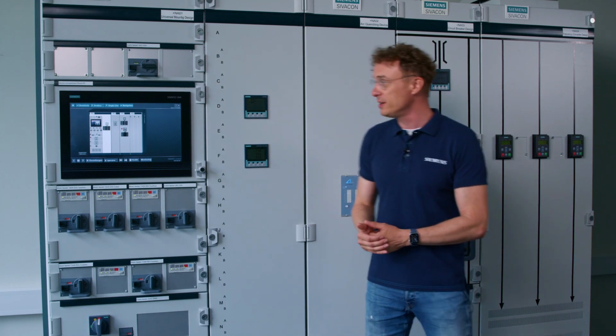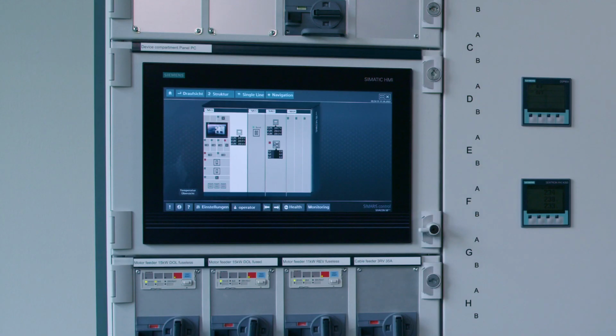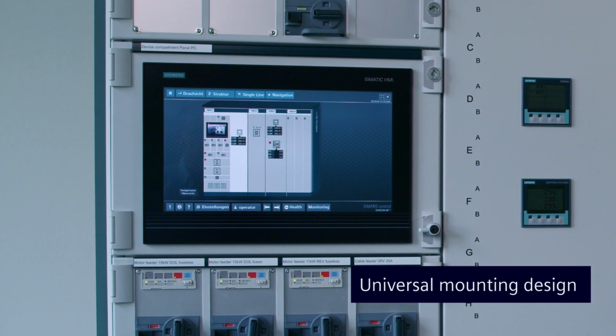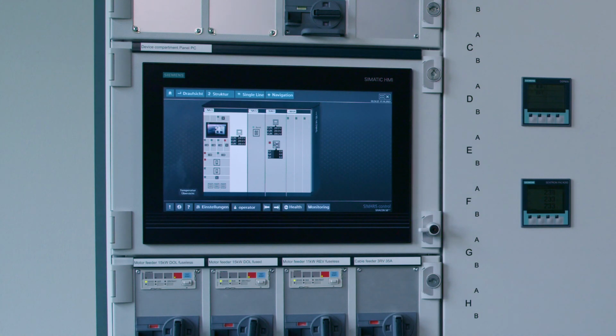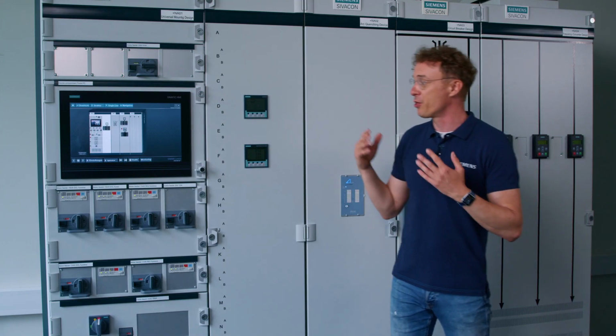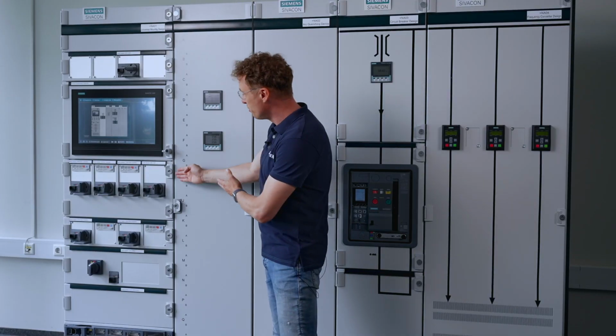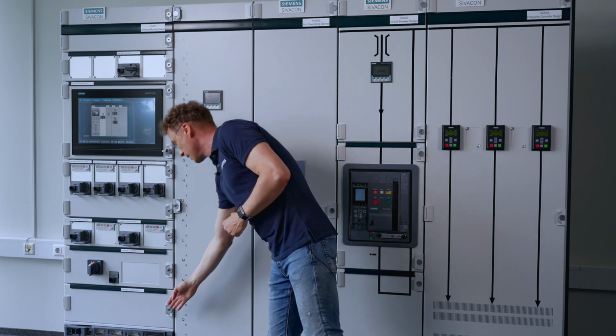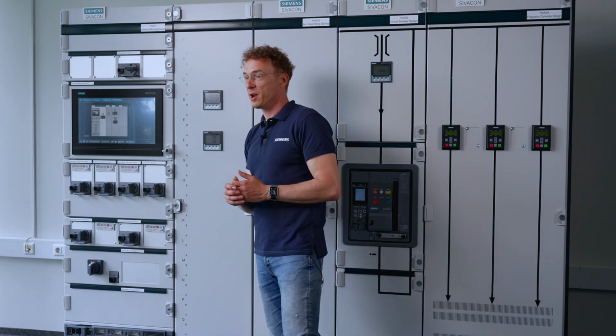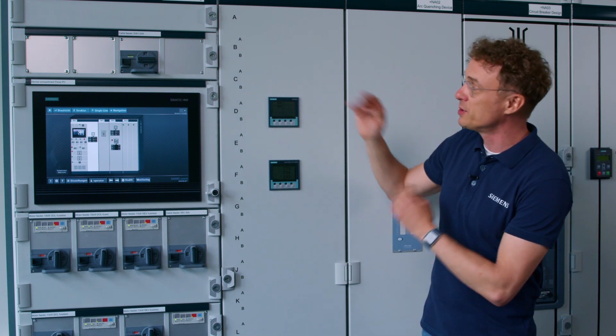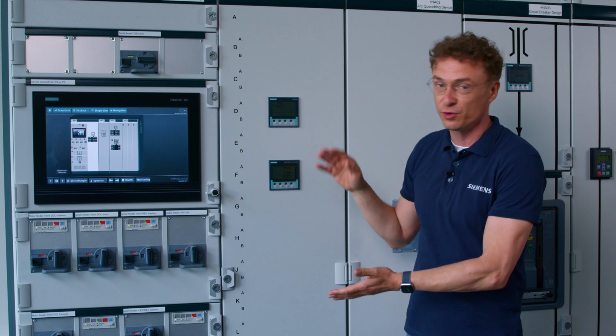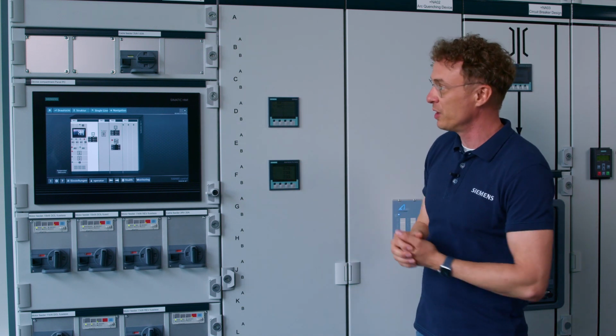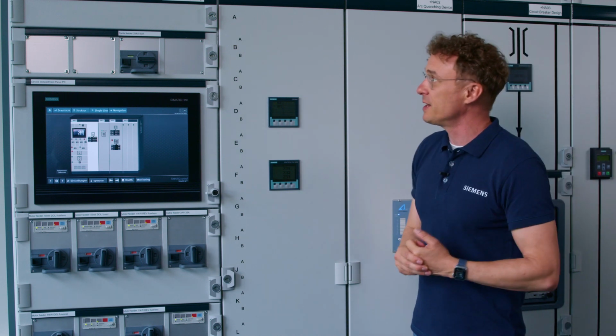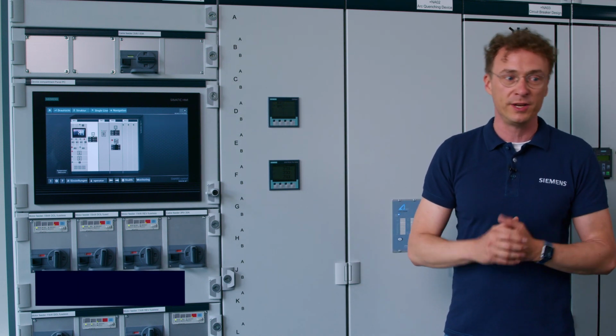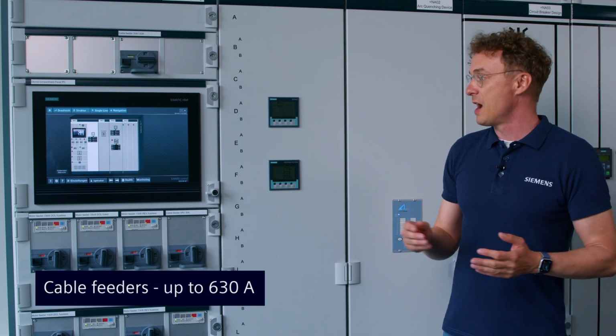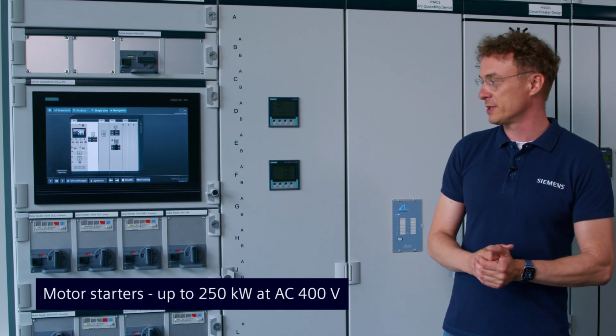Starting from left to right, the first section that we see here is the so-called universal mounting design. Universal mounting means that you can combine the three different installation types: withdrawable units, fixed mounted units, and down here we also have a sample for the plug-in design. You can use the section also exclusively for withdrawable units or fixed mounted design, but as shown here, you can also mix it. The feeders of this section are rated for cable feeders up to 630 amps, for motor starters up to 250 kilowatts at 400 volts.